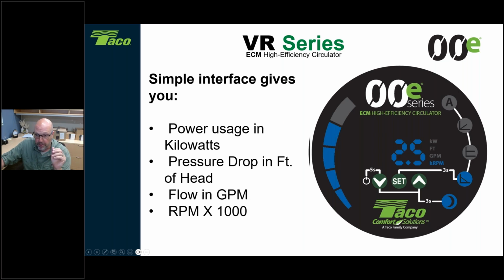I almost forgot. I didn't want to jump off this screen yet. It does also have a night mode. So when you see this picture of the moon, this night mode means the circulator is going to go into an energy efficient mode and drop its speed. However, we don't typically do setback the way this circulator is looking for. This circulator, because as you guys know, Taco is an international company, so we make sure this circulator works on both sides of the pond. So the night mode for this circulator means when the water temperature drops 20 degrees, all right, the delivery water temperature drops 20 degrees in less than an hour, the circulator will start to run at a slower, reduced speed.